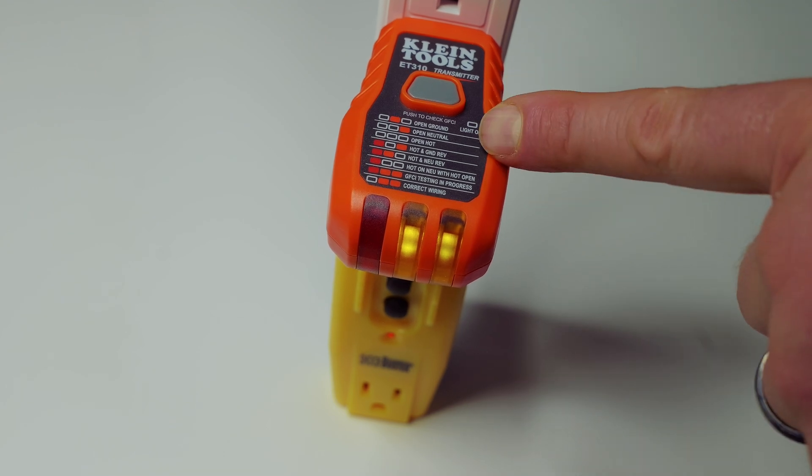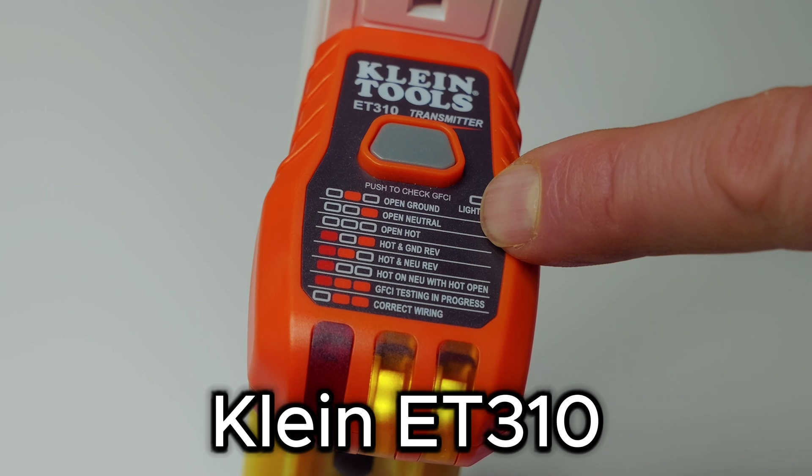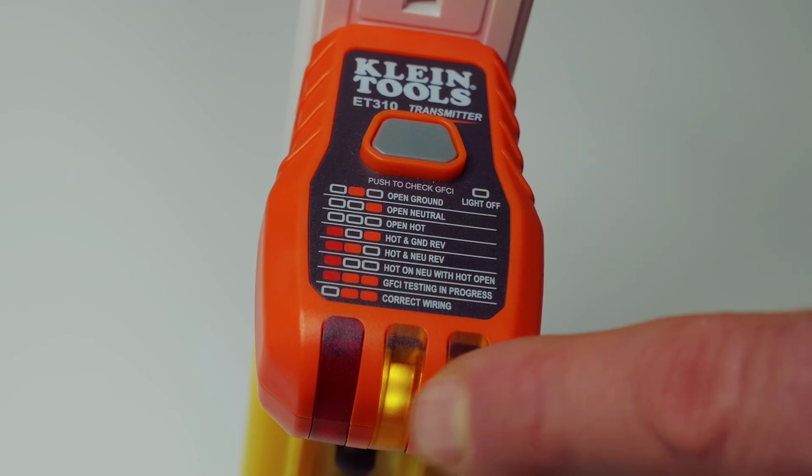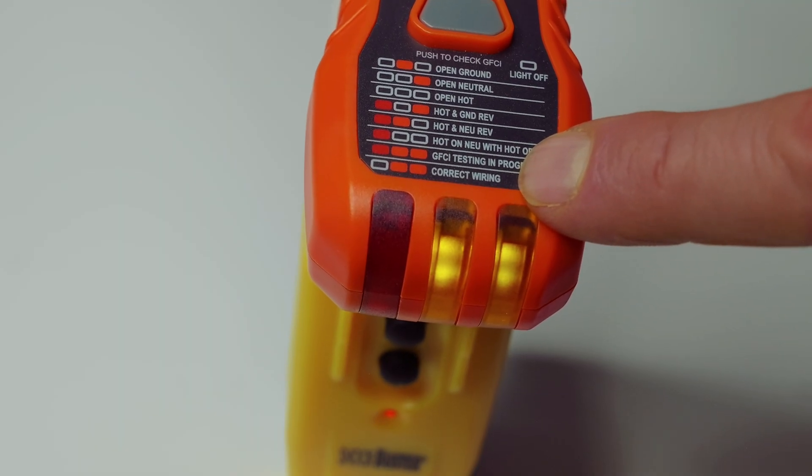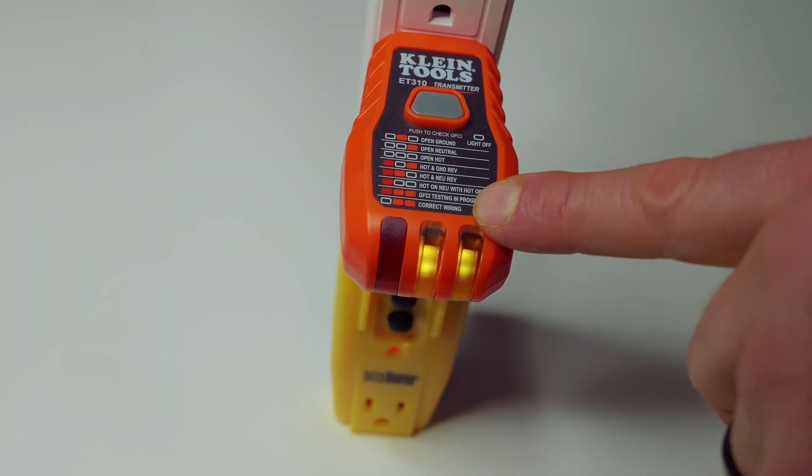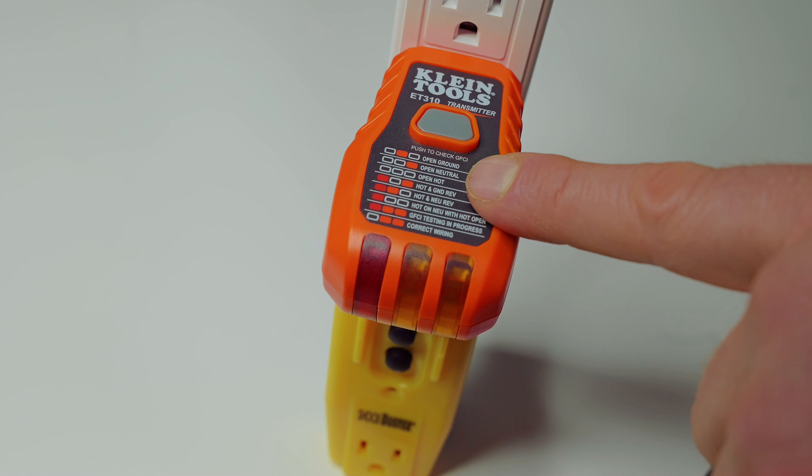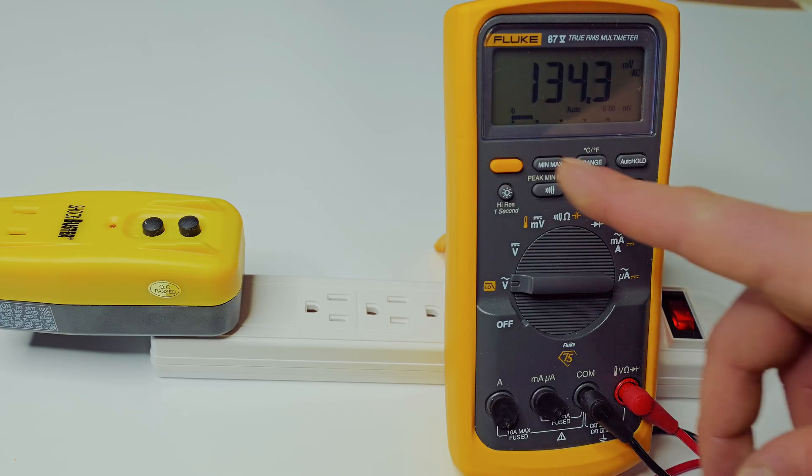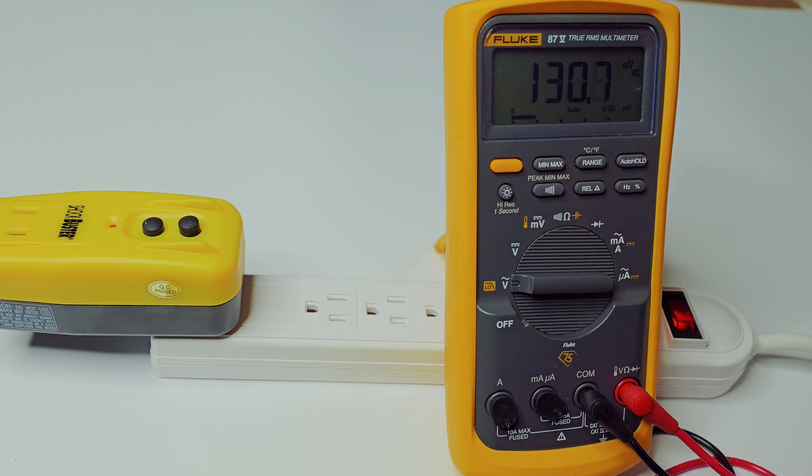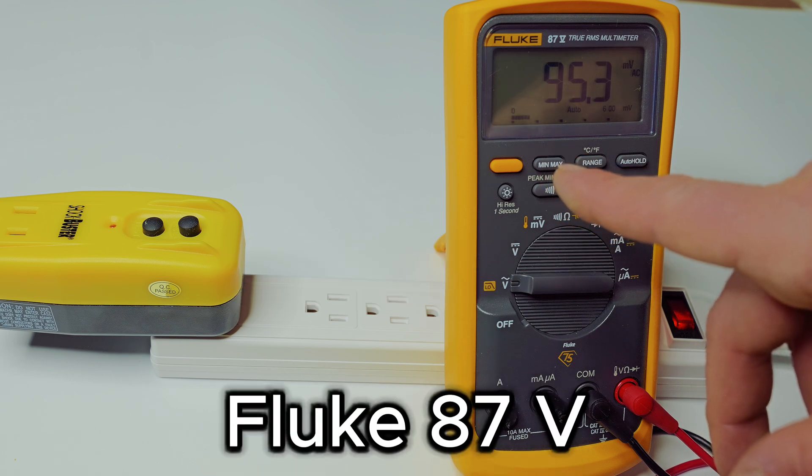Now folks as promised I'll go ahead and show you a few safe alternatives. This is a Klein's tool ET310. What this is doing right now is telling me I have two green lights here which means my circuit is wired correctly and it also tells me that there is power to the strip. Now if I were to turn power off obviously my lights are off. So this is another safe alternative in addition to the non-contact voltage tester pens. Now of course the ultimate way to see if you remove power to the circuit is going to be with a traditional multimeter such as the Fluke 87 Five.